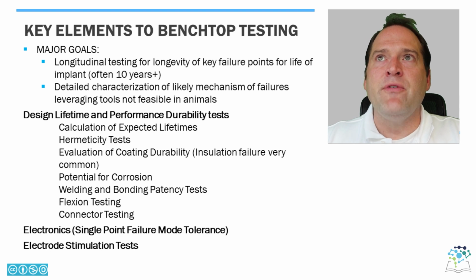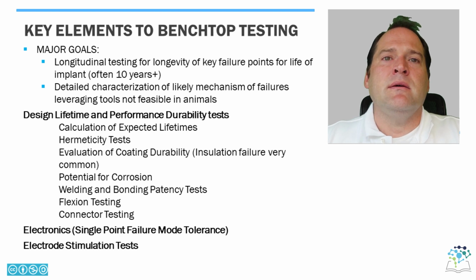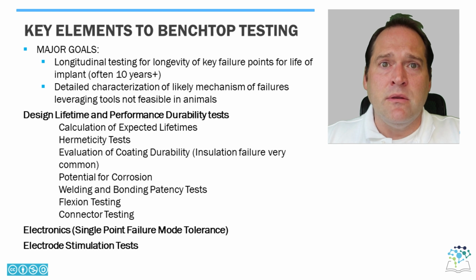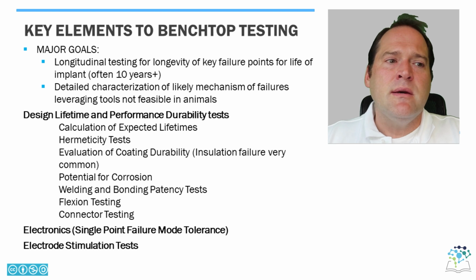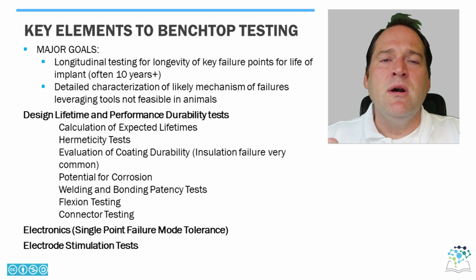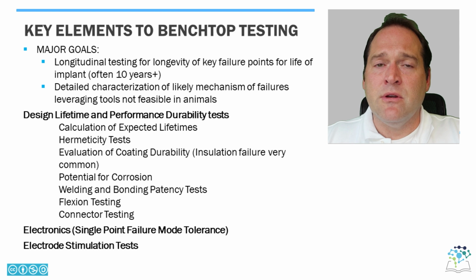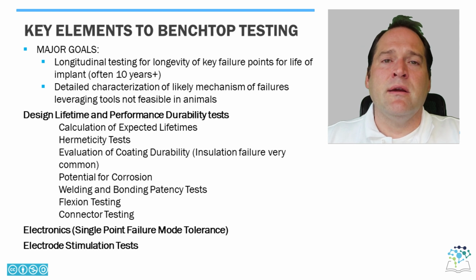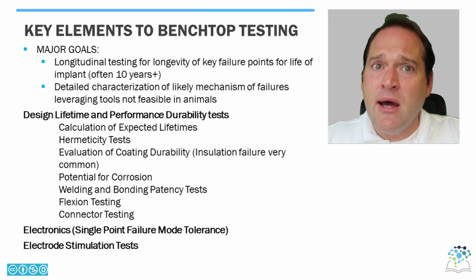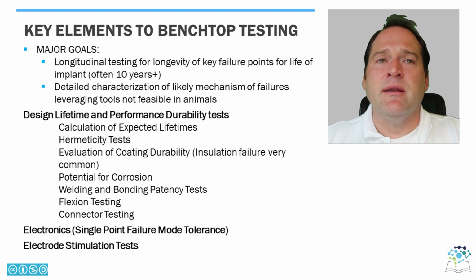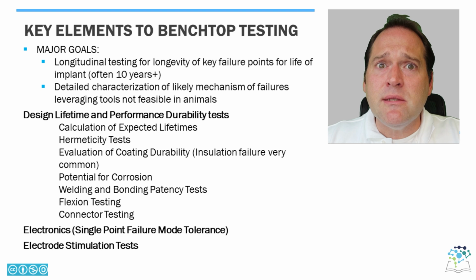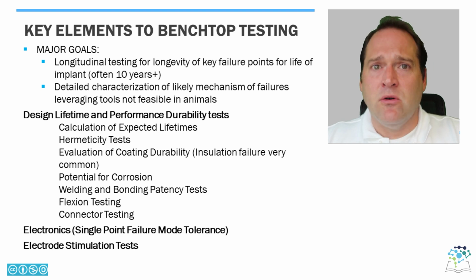And one of the things that's often overlooked in an academic design is that for the most part, you're attempting to develop a device to have what's called single fault tolerance. This means you have to be able to show that if any one component in your device fails, it's not going to create a significant safety risk or a significant efficacy risk, or both. And so many devices that weren't made for regulatory approval are not designed with single fault tolerance in mind, and often have to be substantially redesigned to actually pass single fault tolerance.